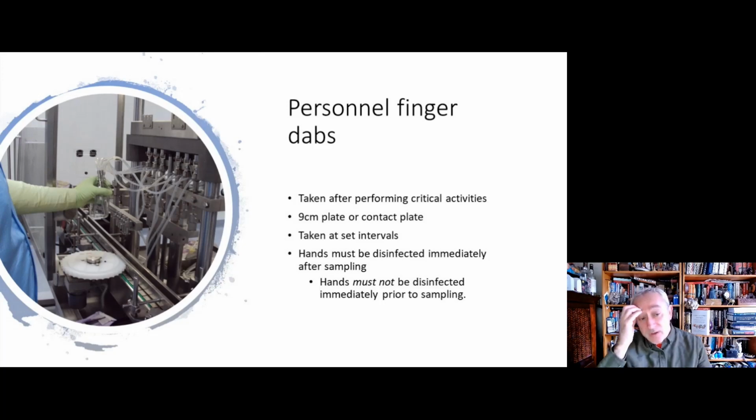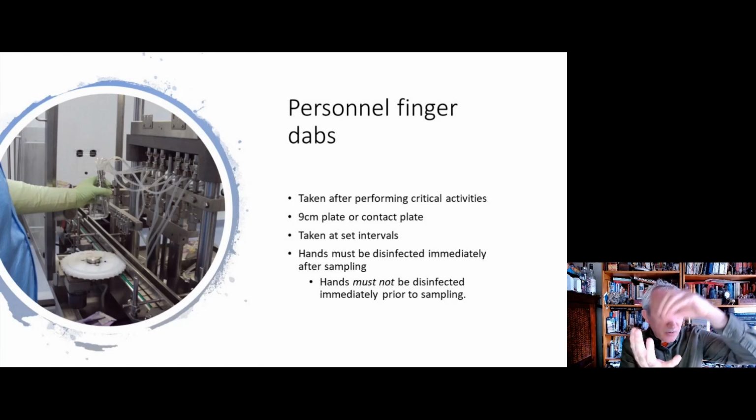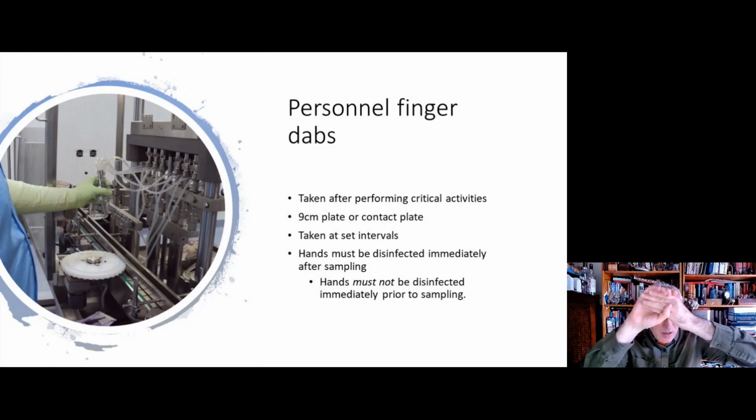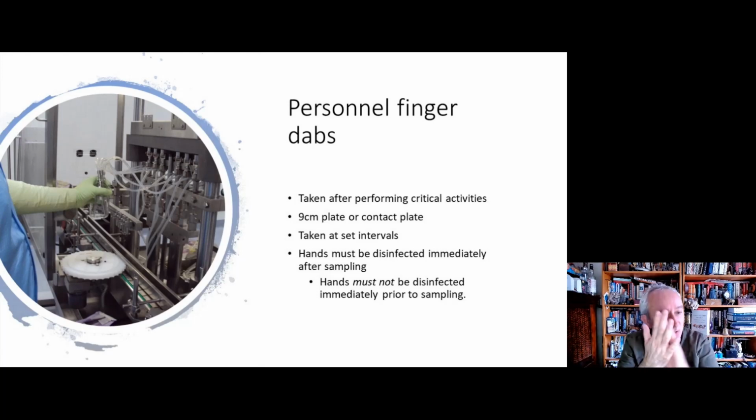So they're always taken after critical activities, and they're always taken at random intervals, and when they've been taken, because there's a risk of little deposits of agar being on there, there needs to be a thorough hand disinfection activity undertaken, and the hand disinfection activity is 1 minute, applying a suitable volume and then ensuring that every aspect of the hands is subject to the disinfectant for a suitably long contact time. So there's always activities like the tips of the fingers, doing the palms, and so on and so forth. And we can look at glove disinfection another time.